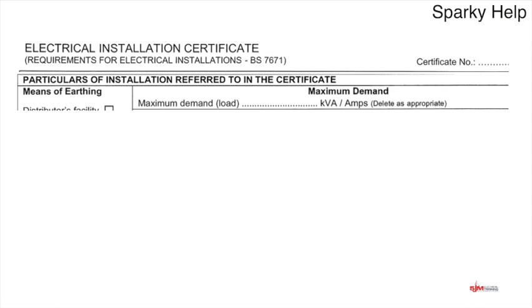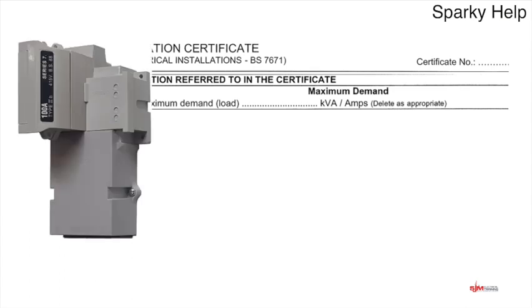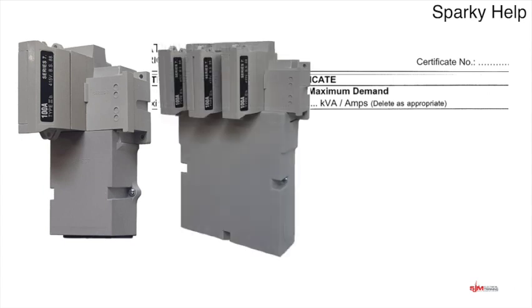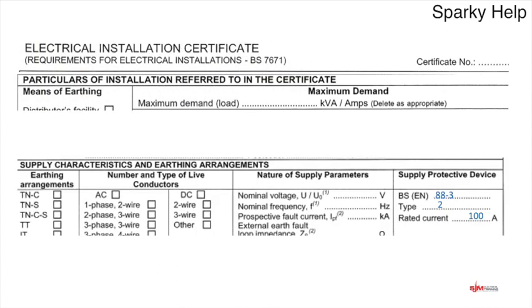The maximum demand can be expressed as either KVA or amps — delete as applicable. What people often do is look at the incoming service head; here we can see a 100 amp supply, and here is a three-phase 100 amp service head. The protective device size gets recorded on supply characteristics, which is part of the electrical installation certificate, shown there as 100 amps, whether single-phase or three-phase.